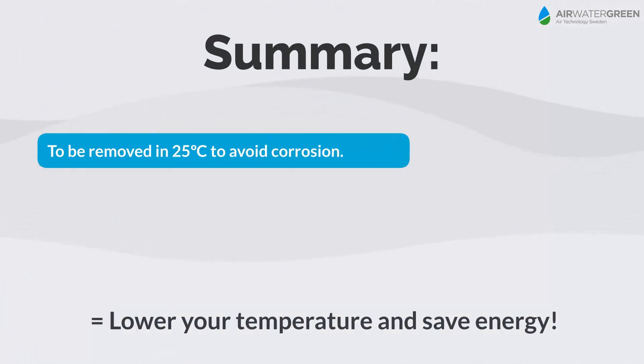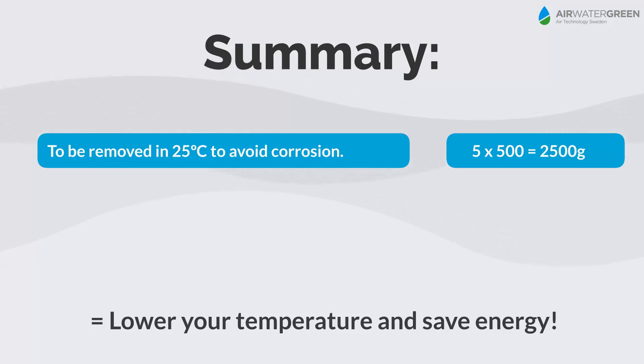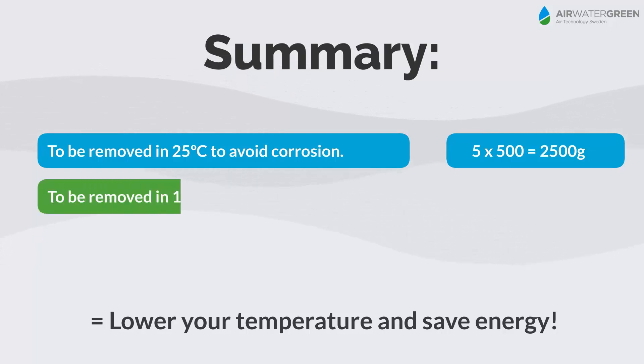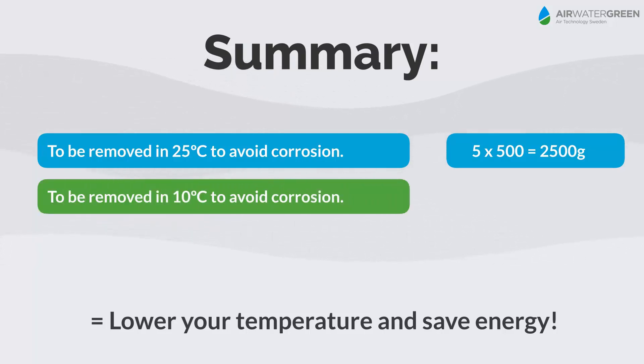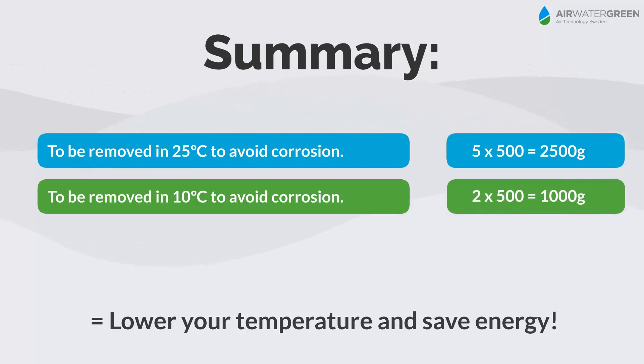Summary — Moisture to be removed at 25 degrees Celsius to avoid corrosion: 5 grams per cubic meter × 500 cubic meters = 2500 grams. Moisture to be removed at 10 degrees Celsius to avoid corrosion: 2 grams per cubic meter × 500 cubic meters = 1000 grams.